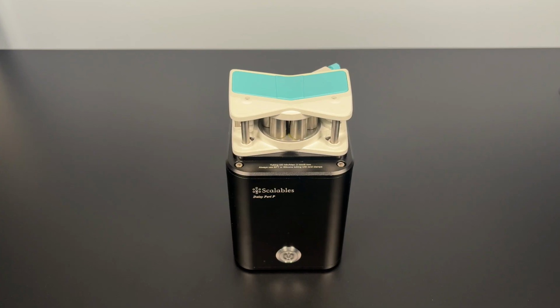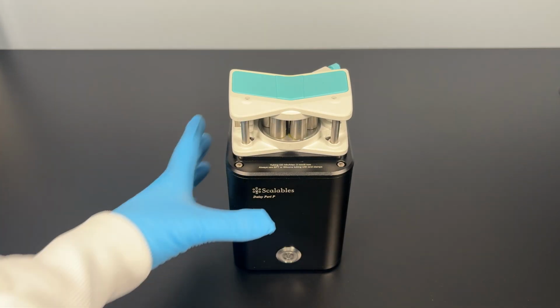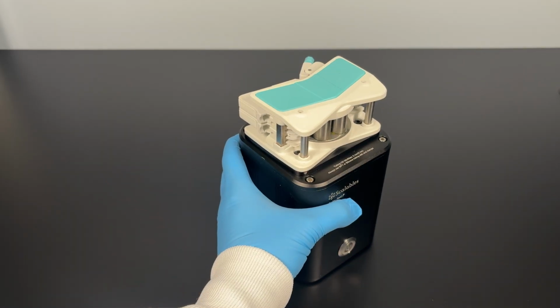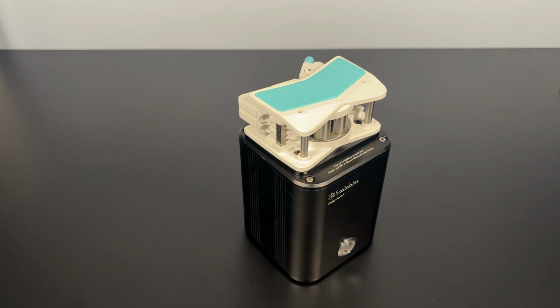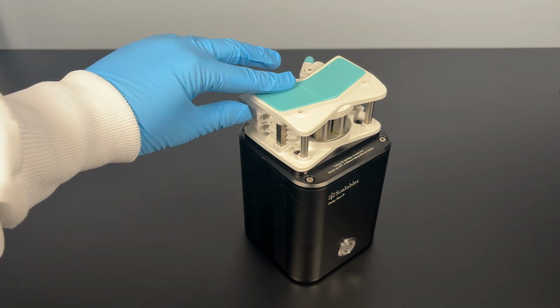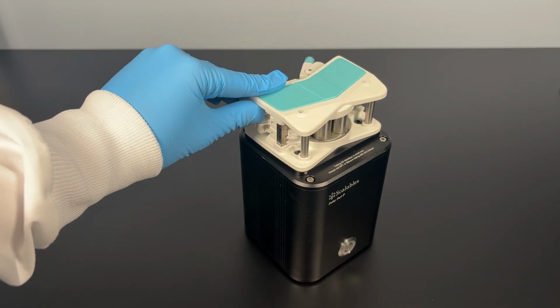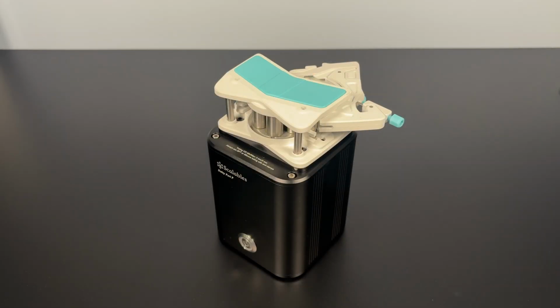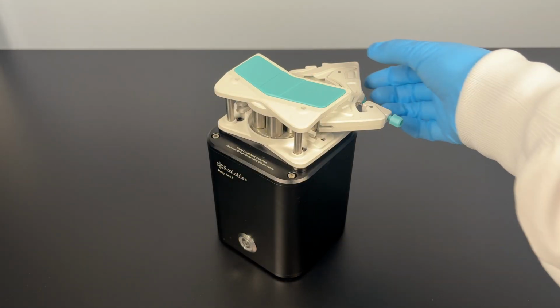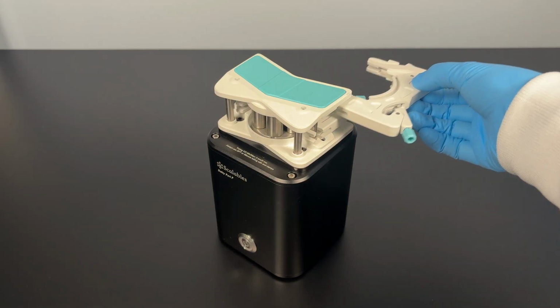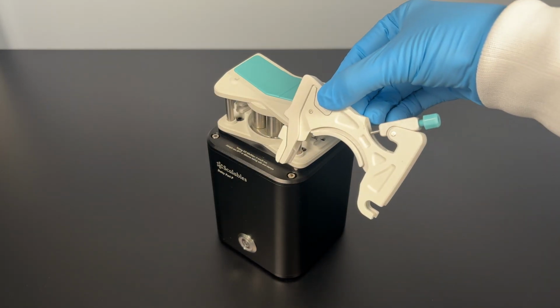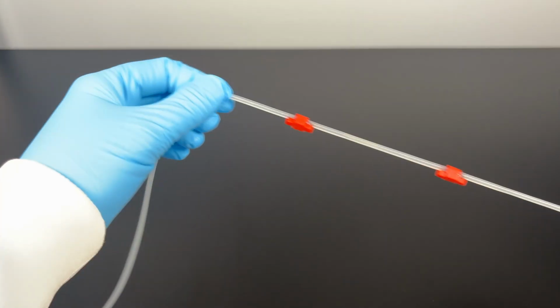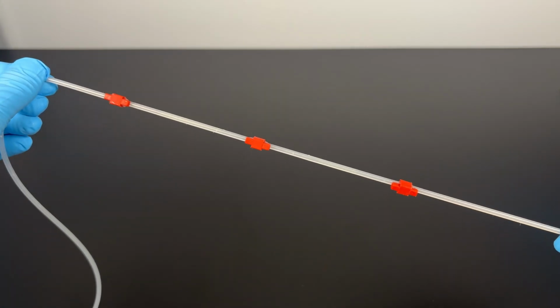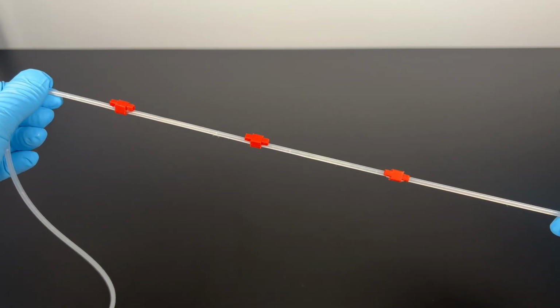This is the Scalables Daisy Peri P, the precision peristaltic pump. The Peri P comes with 2 cartridges. To remove a cartridge, press on the lock arm on the side to allow the cartridge to be released. Next, on the other side, rotate the cartridge to remove the hook from the bar. The Peri P is compatible with silicone tubing or the more durable PharMed BPT.